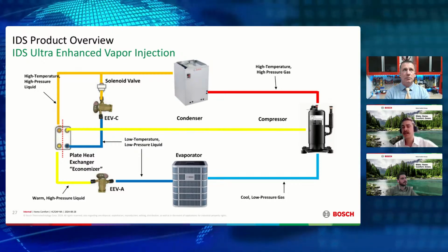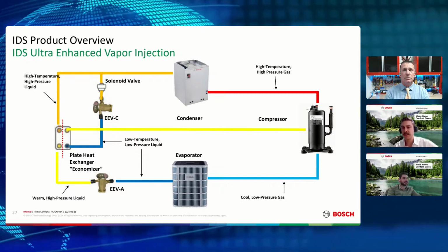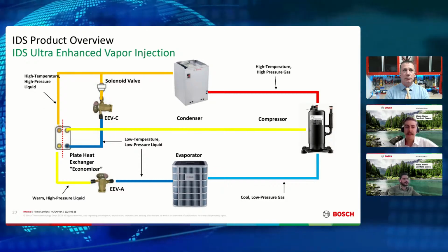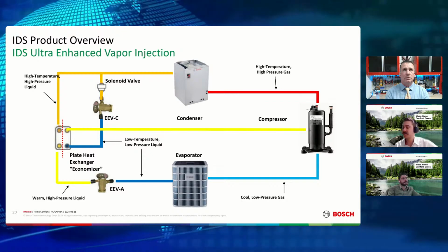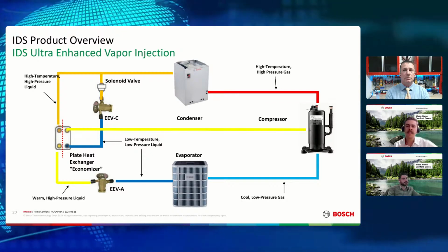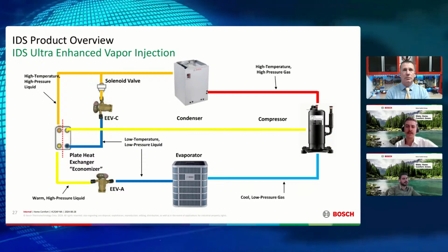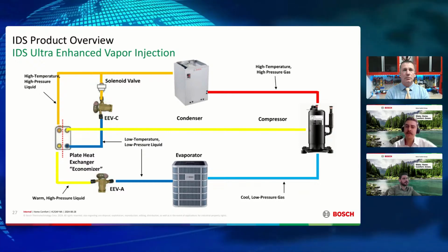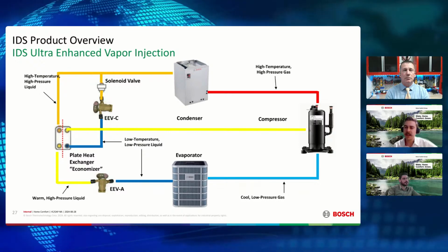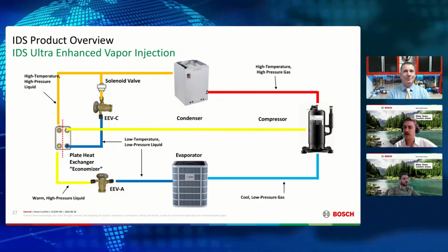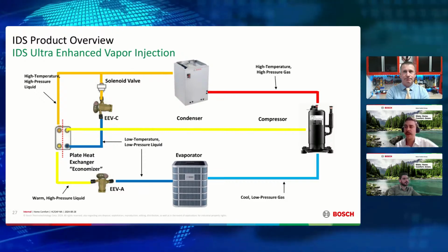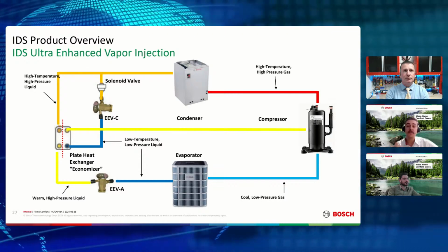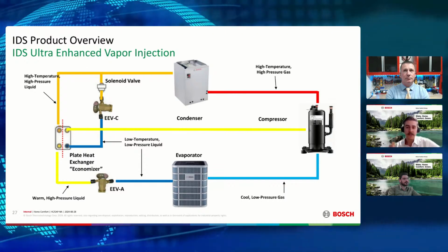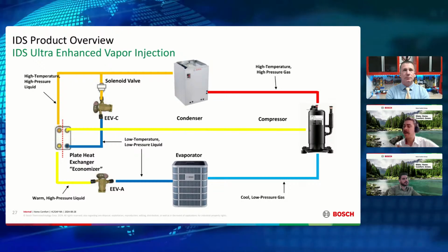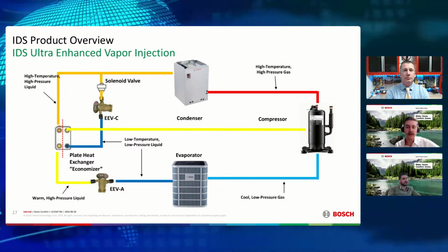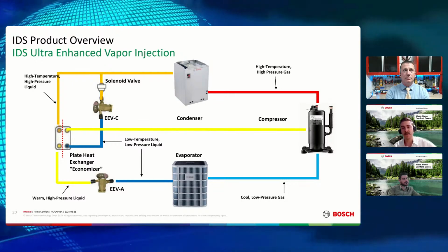We send that portion through an expansion device, EEVC, which is the expansion device for this loop, taking it to an intermediate pressure and temperature. Then we cross it through a plate heat exchanger, counterflow with our main flow. We've chilled this extra bypass, and we boil it off by crossing it with the main flow, which increases our subcooling.